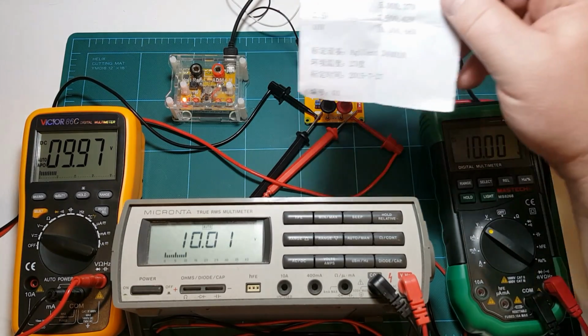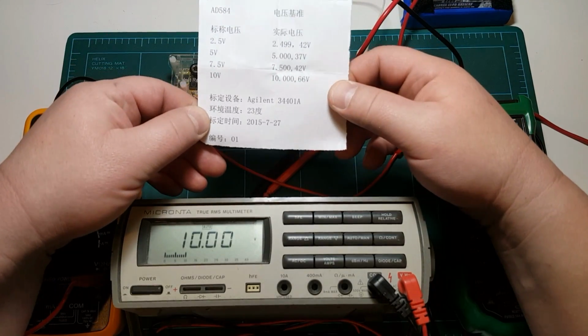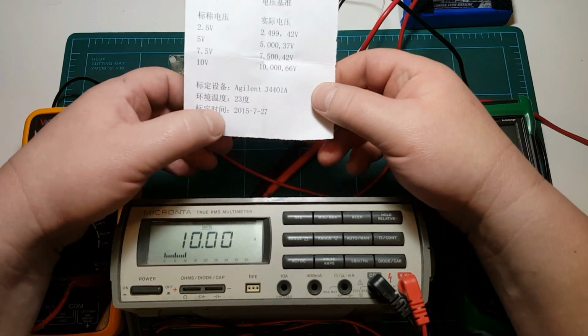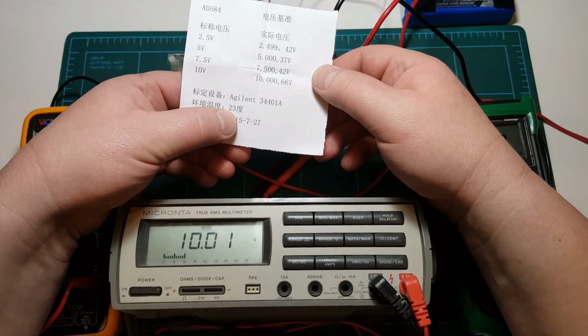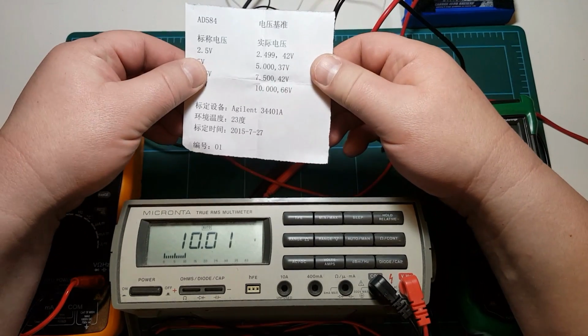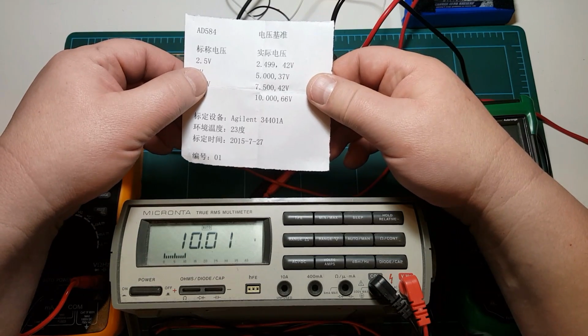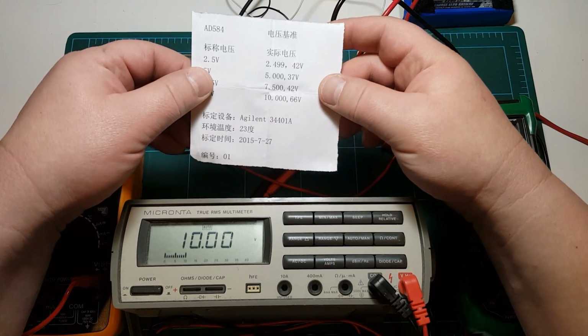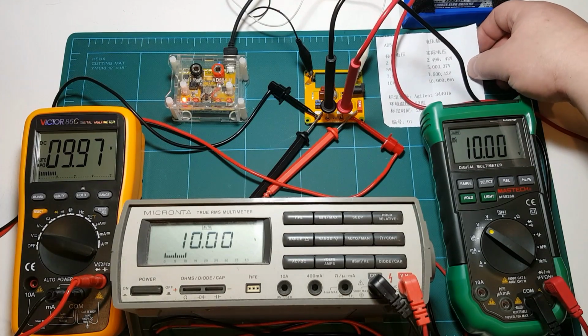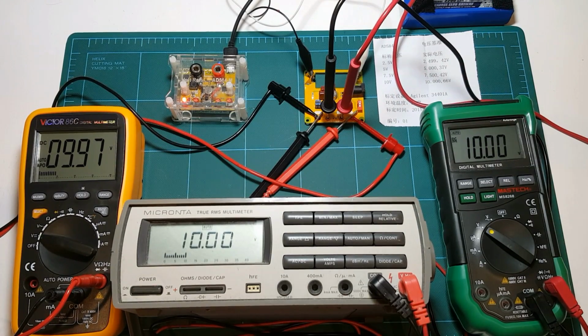Unfortunately, I don't read Chinese, so I'm not sure what all this says - I should probably translate it to make sure, but I'd guess it was measured at 23 degrees Celsius, around 75 degrees Fahrenheit, which is fairly close to the 70 to 73 degrees I keep here. So if there's any difference caused by temperature, it should be negligible. I'm hoping that I am in fact getting 10.00066 volts on this range.